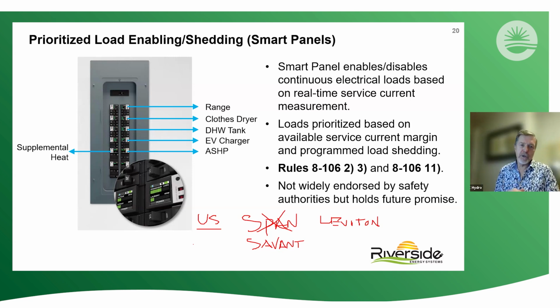I'll just say that the National Electrical Code in the United States is a bit more flexible on the ability to use these smart panels than the Canadian Electric Code, or at least that's what I've been told. Span is spending their time because they can use this to prove that they can keep below certain limits, and by doing so they can change their peaks during the peak period for the utility and help us out, or go off entirely if they have sufficient battery storage. So those types of things are available with smart panels, or will be, once we get the authorities having jurisdiction, the safety authorities, etc., in agreement that these things actually work. So this is emerging technology, I'll say, not highly in application, but certainly the way of the future.